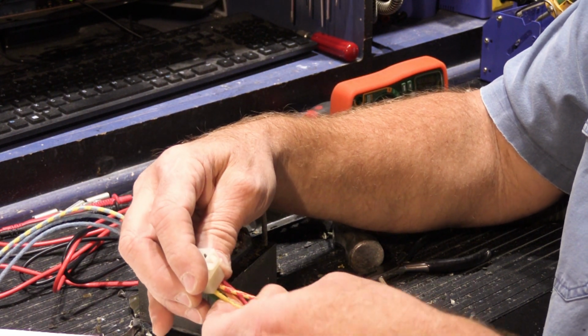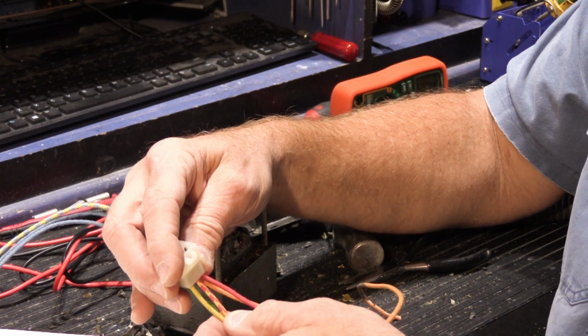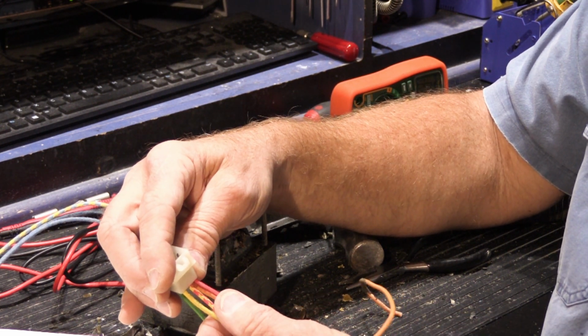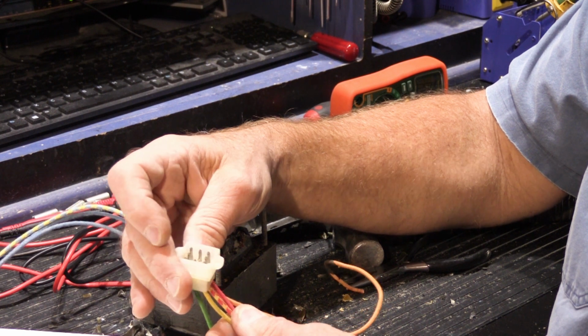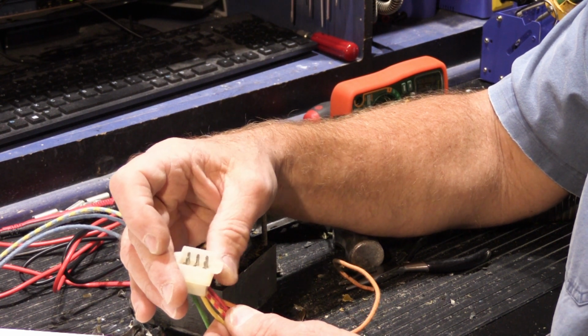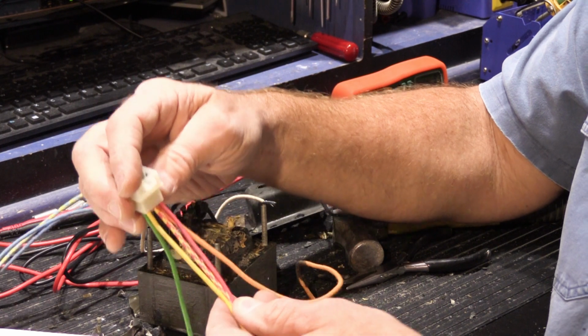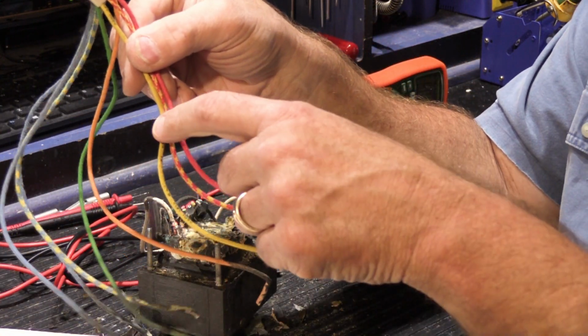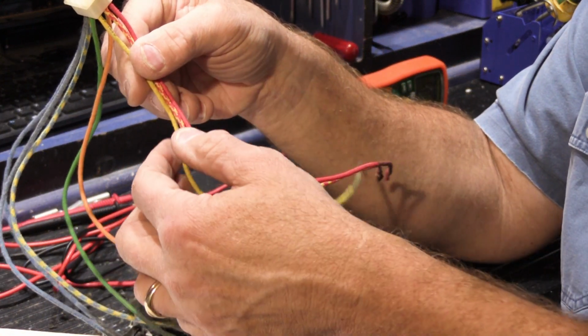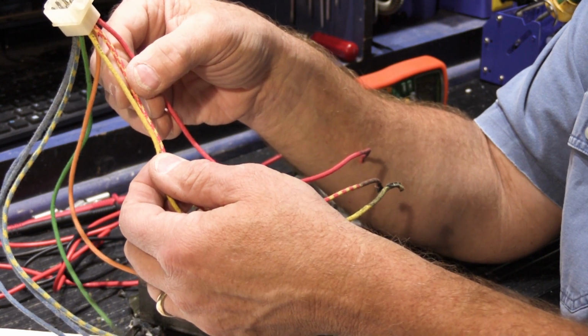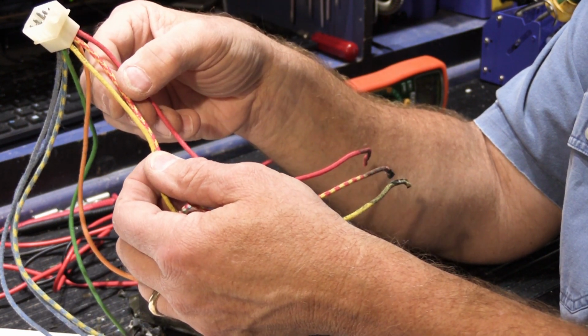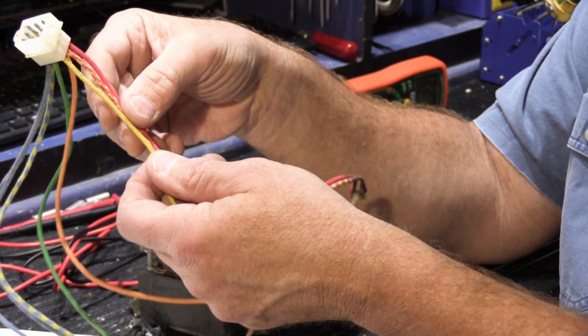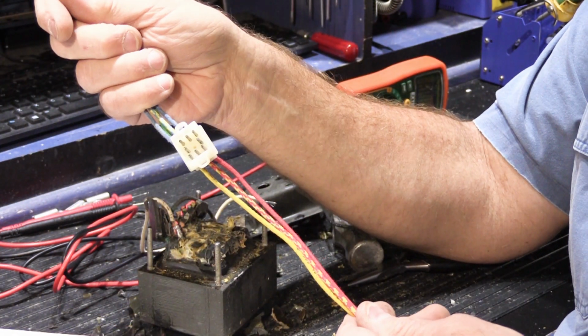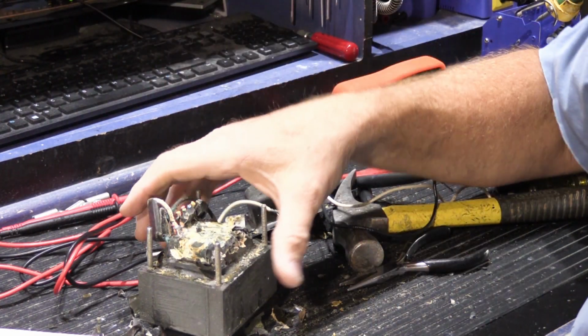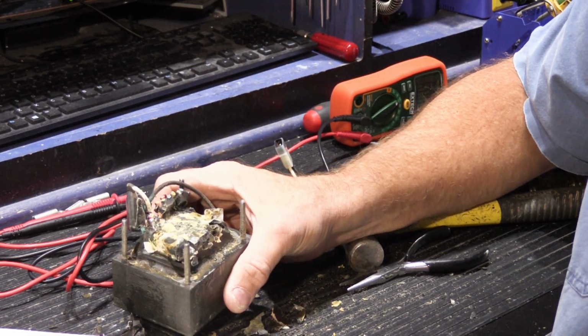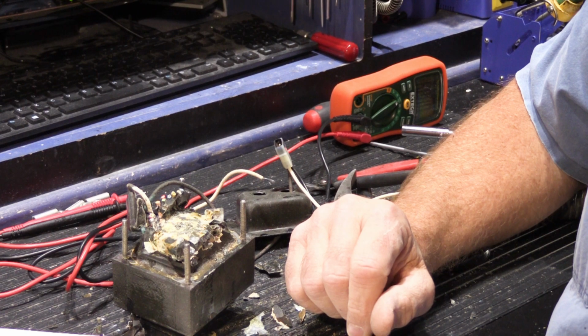Then we have our yellow, red with yellow, and red, shown as 40 volts, and that is a center tap. So between the yellow and the red would be 40, between the red-with-yellow center and the yellow is 20, and red-with-yellow and red would also be 20. So you've got two center taps. Your transformer has two sets of secondary windings, one a multi-tap, one a center tap.